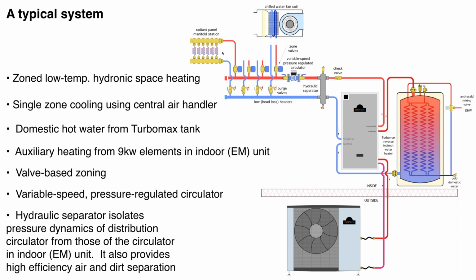And I've just set up a very typical system where we may have, in this case, 3 zones of space heating. I'm showing low temperature heat emitters like radiant panels. And again, it could be floor heating, it could be radiant walls, radiant ceilings, but it could also be other heat emitters. It could be fan coils, it could be panel radiators, and it could also be a combination of those emitters. So you have a lot of versatility in terms of how you select a palette of heat emitters depending on what those project requirements are. And I'm also showing a fan coil here. Now this fan coil could be used in heating mode, but I'm showing it as a cooling mode. So when the unit is generating chilled water in the summer, this zone would open, the circulator would be on, and we would be pumping chilled water up through that fan coil. So we have heating and cooling taking place on, in this case, the left side of this hydraulic separator.